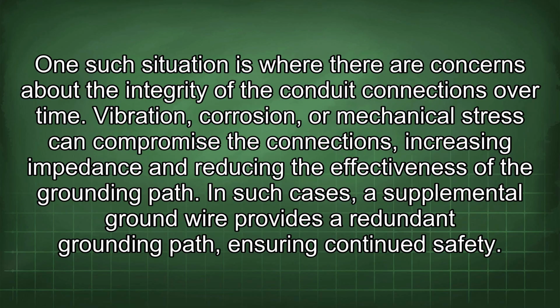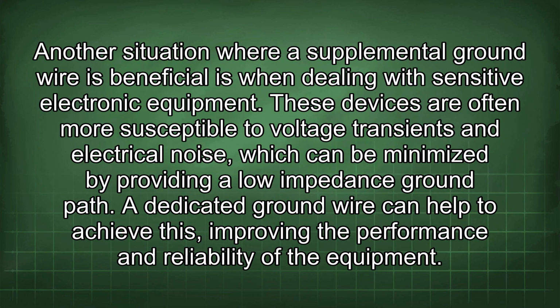One such situation is where there are concerns about the integrity of the conduit connections over time. Vibration, corrosion, or mechanical stress can compromise the connections, increasing impedance and reducing the effectiveness of the grounding path. In such cases, a supplemental ground wire provides a redundant grounding path, ensuring continued safety. Another situation where a supplemental ground wire is beneficial is when dealing with sensitive electronic equipment. These devices are often more susceptible to voltage transients and electrical noise, which can be minimized by providing a low impedance ground path. A dedicated ground wire can help to achieve this, improving the performance and reliability of the equipment.